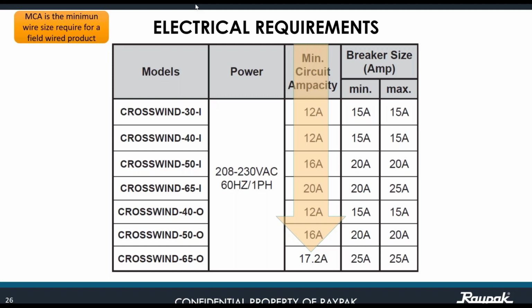Okay, so for the minimum circuit ampacity, you only use 12 amps for the 30 and 40,000 BTU. For the 50, you need 16 amps, that is the minimum. And for the 65 it is 20 amps. That is the initial amps that the unit is going to be drawing. But the breaker size has a minimum and maximum. For the 30,000 it is going to be 15 and 15 amps, minimum and maximum. Same for the 40,000 BTU, 15 and 15 amps. For the 50,000 BTU it is going to be 20 and 20. And for the 65,000 it is going to be 20 minimum and 25 maximum breaker size.